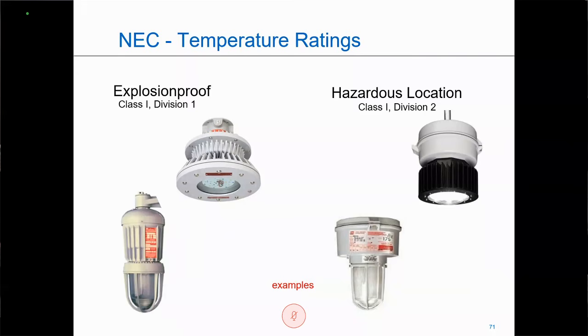Typically speaking, I don't usually find anybody taking advantage of the 80% rule, because then you'll need to know what those surface temperatures are of that particular unit. So in Division 2, usually I always see clients, with rare exception, use the rated Division 2 fixture because it has all those temperature markings on it that you don't have to worry about those yourself.